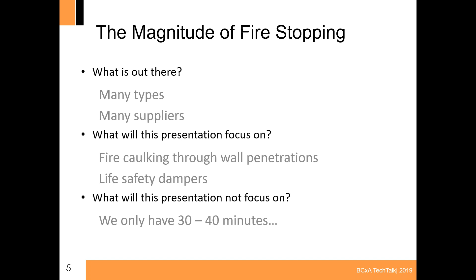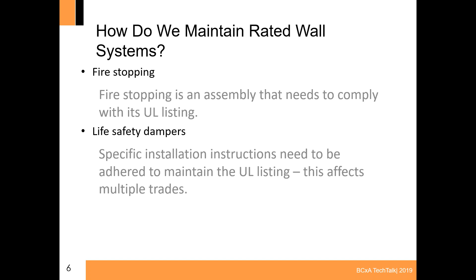So how do we maintain our rated wall systems? There's fire stopping techniques and life safety dampers, and these are both UL listed assemblies, meaning they're tested in a specific manner for installation. To maintain that UL listing, you need to install them the specific way they were tested. If you ever deviate from that, it comes down to engineering judgments. So it's important to follow those installation instructions.